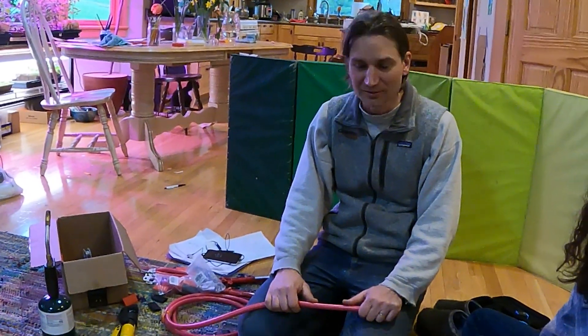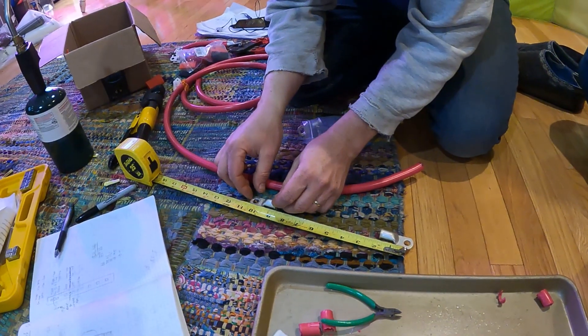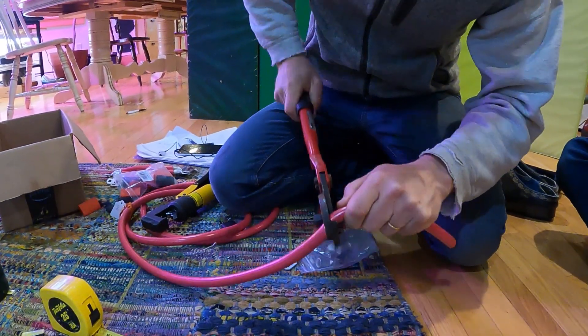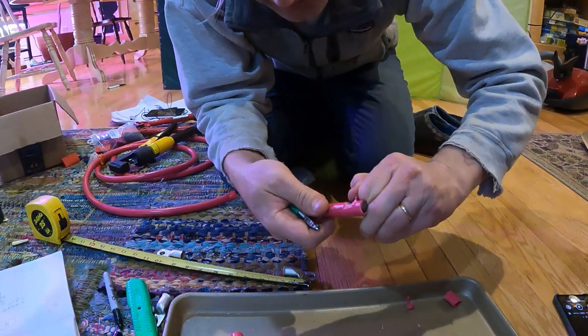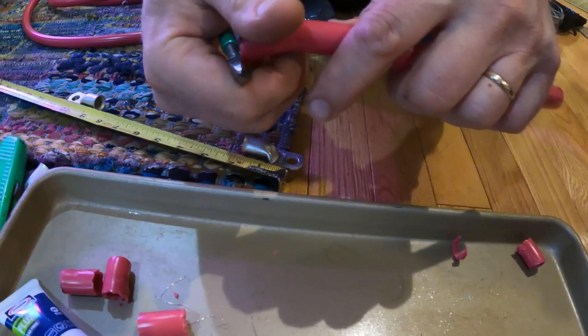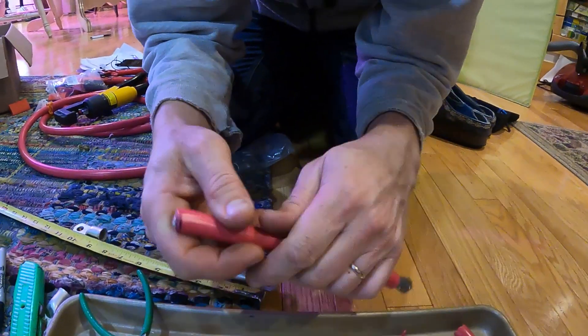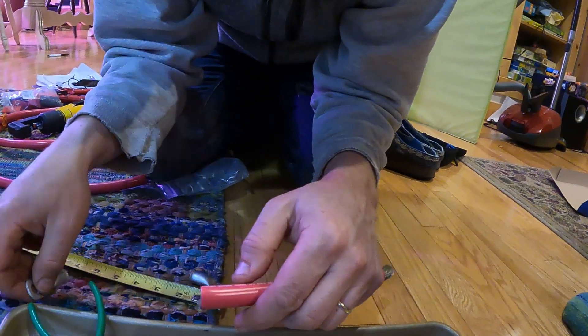We're making battery cables now for connecting up the different stacks of lithium-ion modules. I'll put these where I think they belong and mark them at the right length. These kinds of wires are so flexible because they have so many little strands of wire inside of them, but it's really easy to break some of those wires. This is two-aught wire, and it's Ancor marine wire.